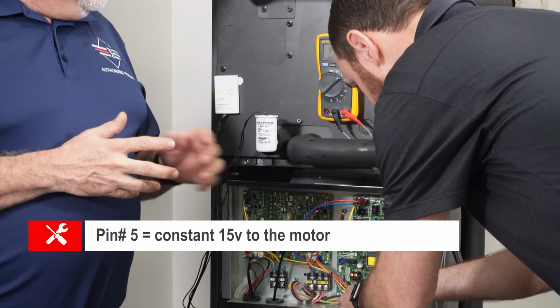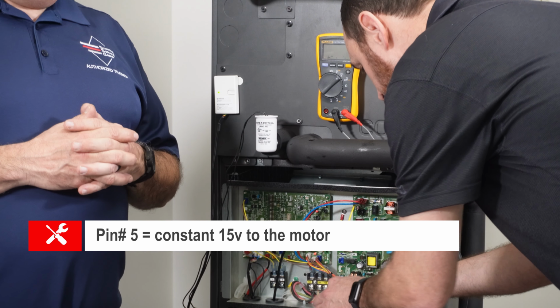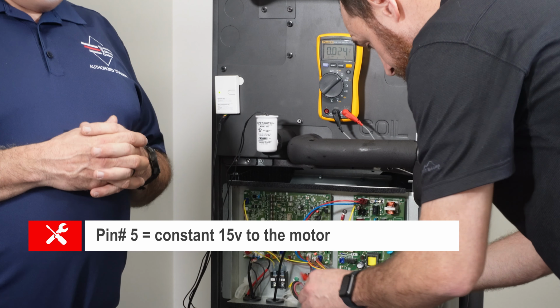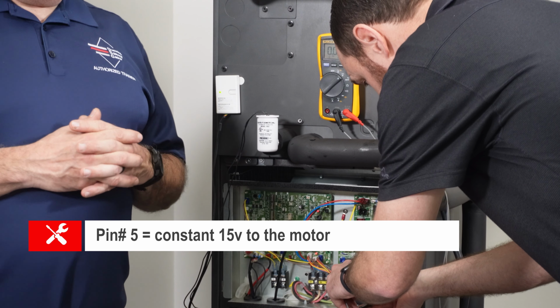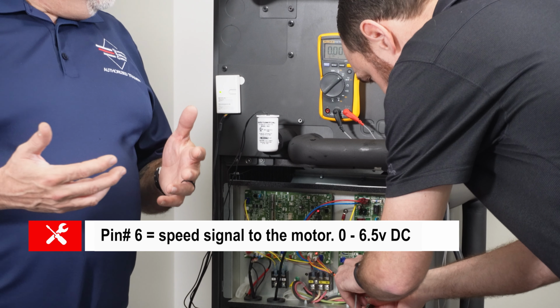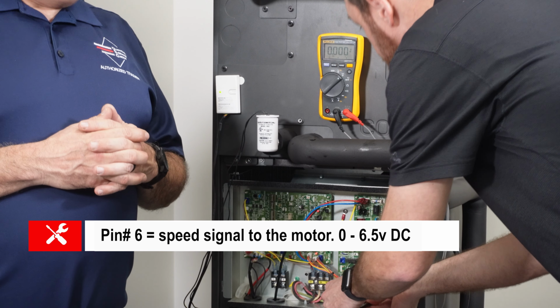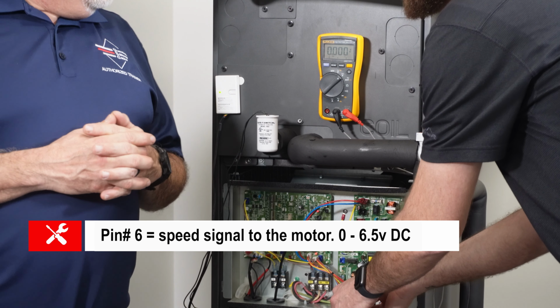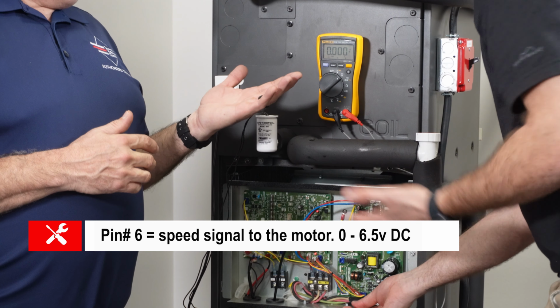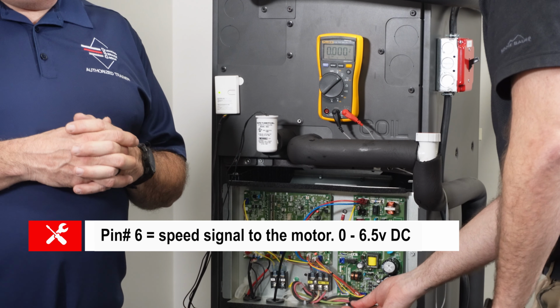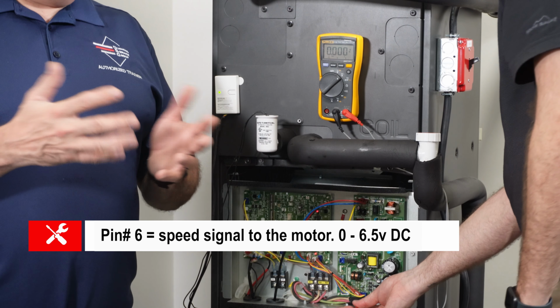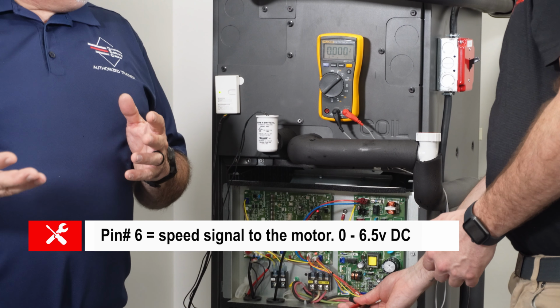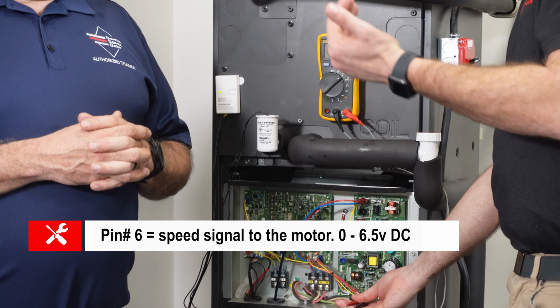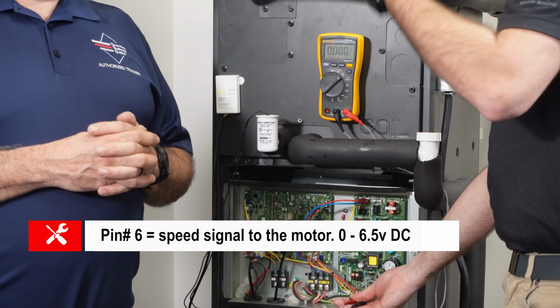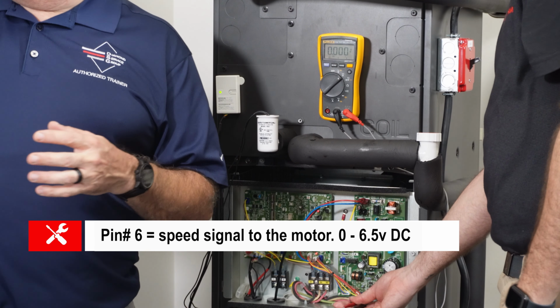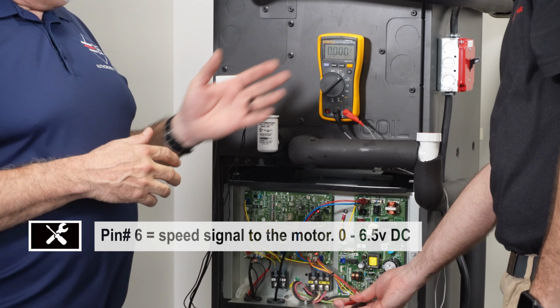Now we're just going to leave one meter lead on the common and hopscotch to the other pins. We're going to pin number 6 now. This is our speed signal to the motor, from 0 to 6.5 volts DC. Right now our system's off, so we're seeing 0. But if it was running on low speed, we could see maybe 1 volt, and medium speed, a couple more. This is also a good check between low, medium, and high speed. If we went to a controller on the wall and adjusted the fan speed, that voltage would change.